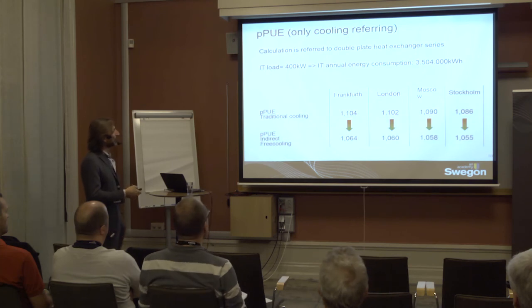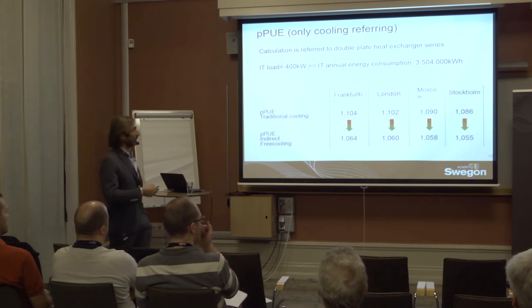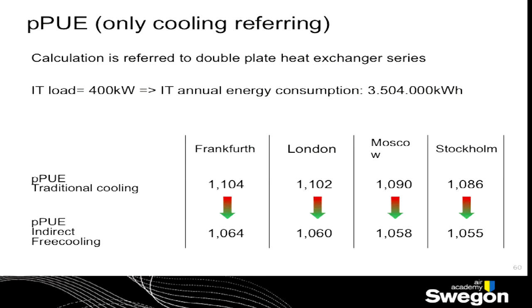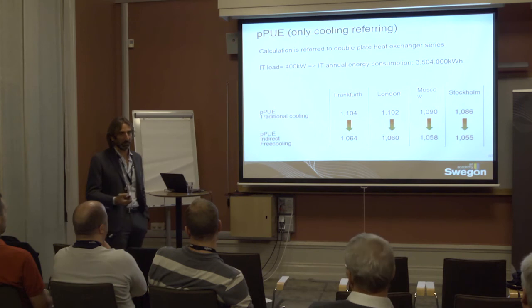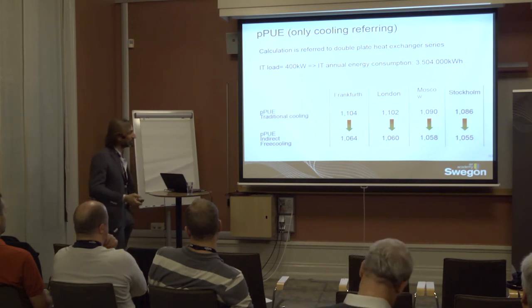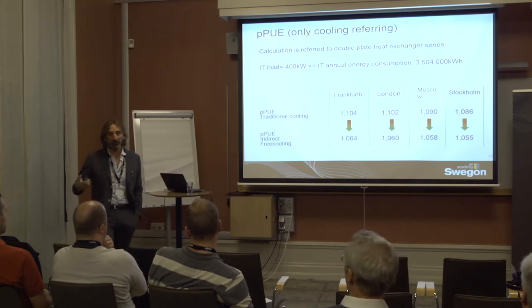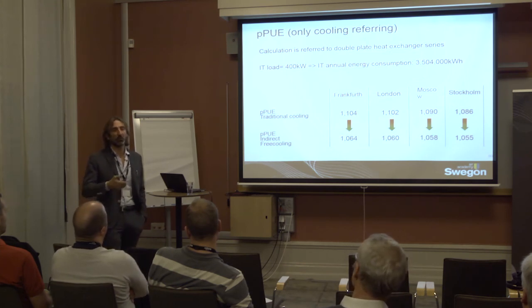And the result that we obtained in terms of partial PUE, of course, not of total PUE, because we cannot take care about the other systems. We cannot take care about batteries. We cannot take care about the lighting or something like this. So don't trust who gives you a number for a cooling system and speaks in terms of total PUE, because it's not possible to consider the total PUE. We should speak about the EER of the system. But we can speak about the partial PUE just in the same way, because if you have got a free cooling system with an EER of 10, it means that you have got a partial PUE of 1.1.